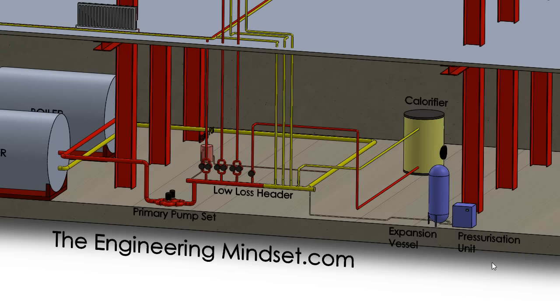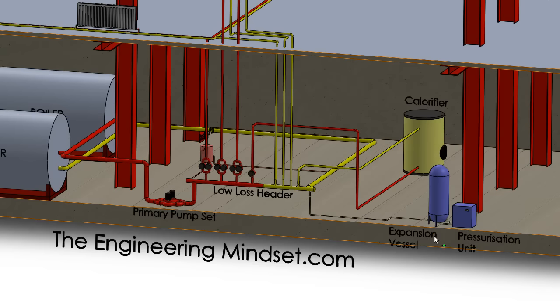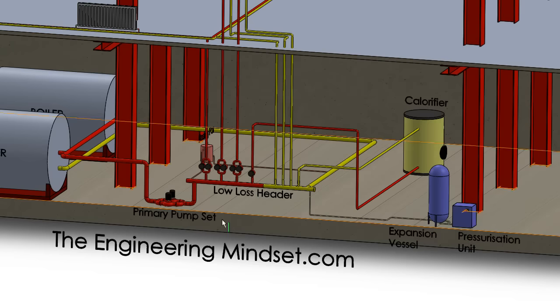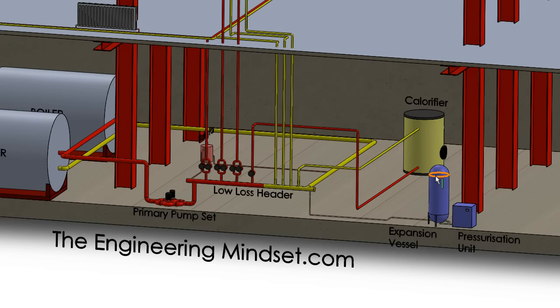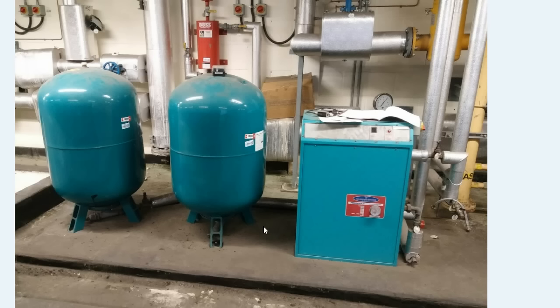So this expansion vessel and the pressurization unit is plugged in somewhere around the low loss header — there are a couple of places it could be, but it's usually located here. And that's just looking at the pressure there and reacting to it. So if it gets too high, then the expansion vessel will take some of that, and when it gets too low the pressurization unit will force that back into the system to equalize it. The pressurization unit will probably look something like this, where you've got the expansion tanks and vessels over here, and then the main pressurization unit just there as well.